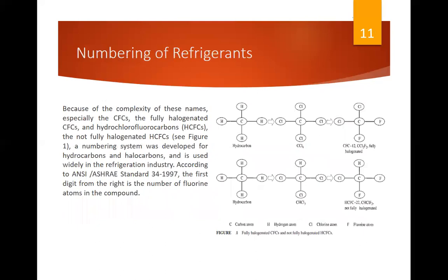Numbering of refrigerant. So, because of the complexity of this name, especially the CFC, the fully halogenated CFCs and hydrochlorofluorocarbons (HCFCs), the not fully halogenated HCFCs, see figure 1, a numbering system was developed for hydrocarbon and halocarbon and is used widely in the refrigeration industry. According to ANSI/ASHRAE standard 34-97, the first digit from the right is the number of fluorine atoms in the compound. Like this one. 2.